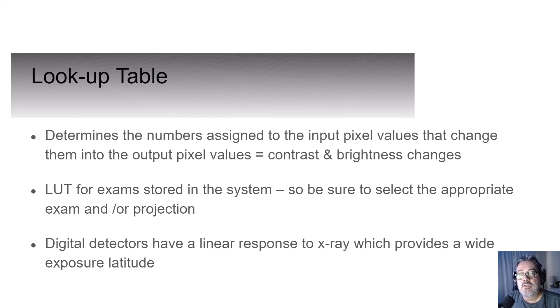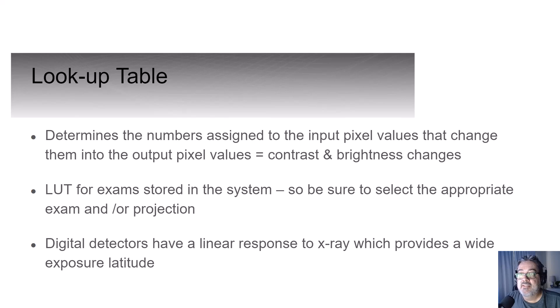The lookup table determines the numbers assigned to the input pixel values that change them into the output pixel values — it changes the brightness and contrast to look optimum. Selecting the wrong body part or projection, as we saw last time, will affect the outcome based on the assigned lookup table. If you process a lumbar spine under an AP abdomen, the image is going to look washed out and have lower contrast than desired.